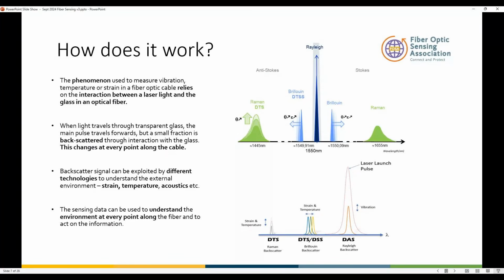Raman distributed temperature sensing uses the anti-Stokes peak at 1445 nanometers and compares it to the Stokes peak at 1655. The Stokes peak is temperature independent, while the anti-Stokes peak is temperature dependent. By comparing those two, we can make an accurate measurement of temperature along the fiber optic line.